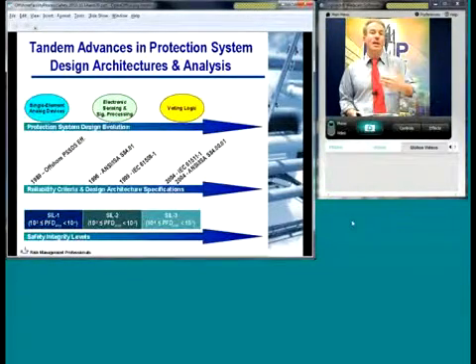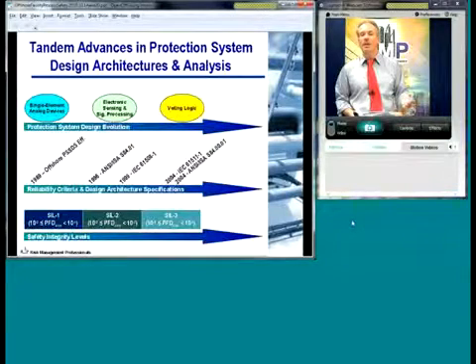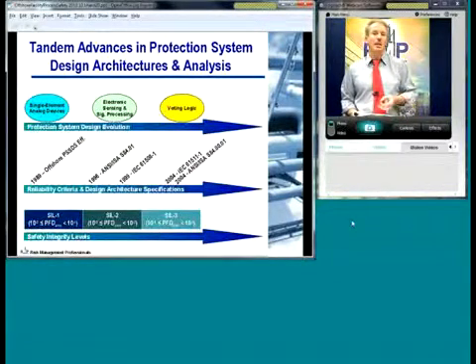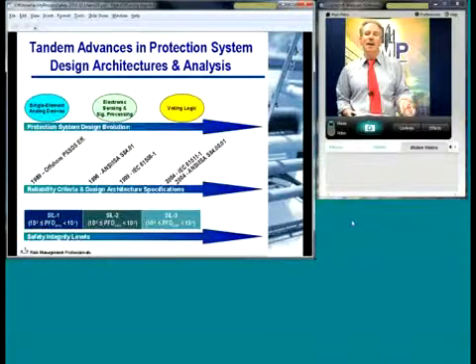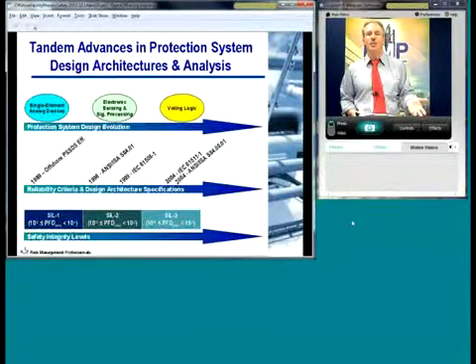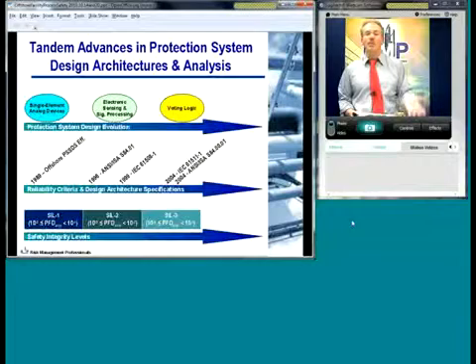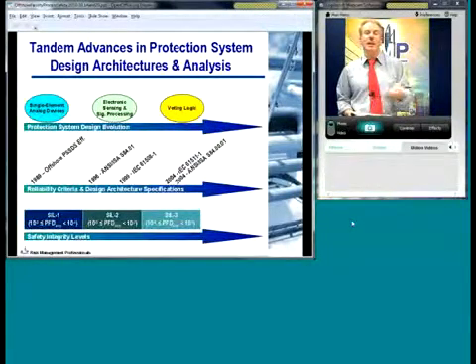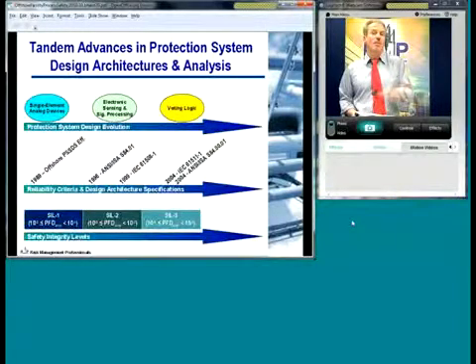Now, in parallel to that, what you want to keep in mind is that there have been changes in guidelines for how to address those. This offshore platform safety shutdown system effectiveness study was done in the late 80s and documented in 1990. In 1996 came the first concepts of applying safety instrumented systems through ISA S84, which was updated later in 2004. And internationally, in 1999, IEC came up with similar guidelines for safety instrumented systems.